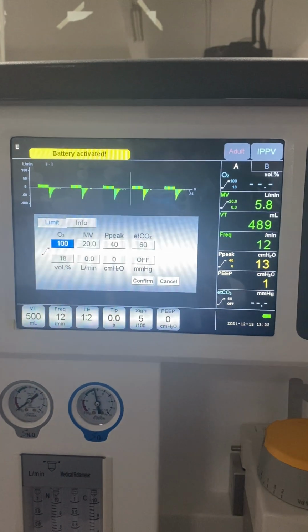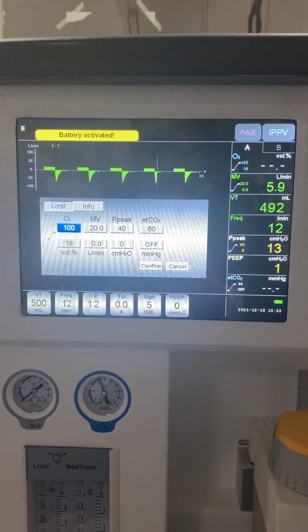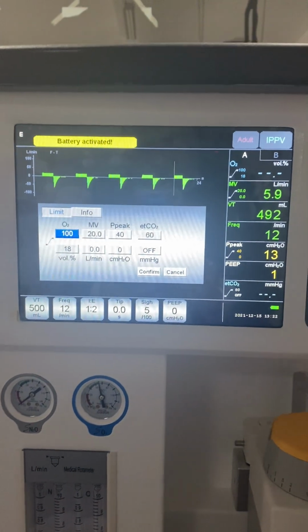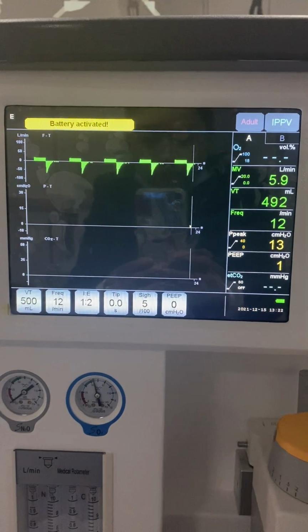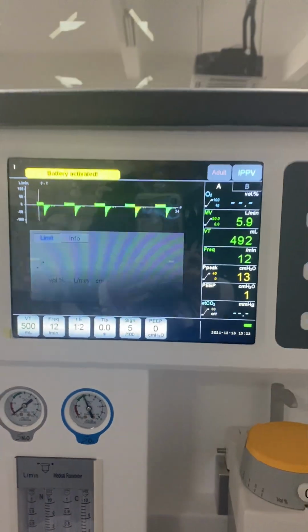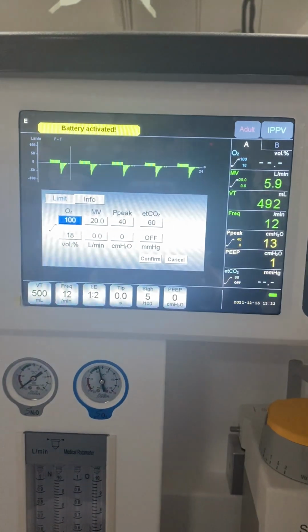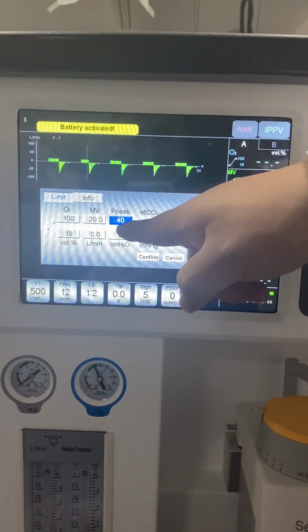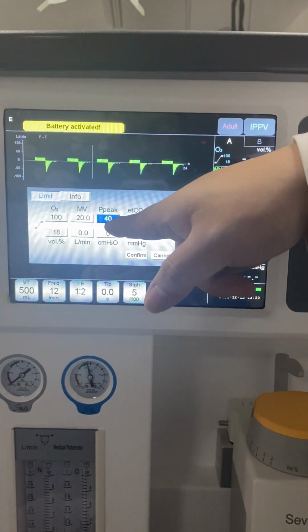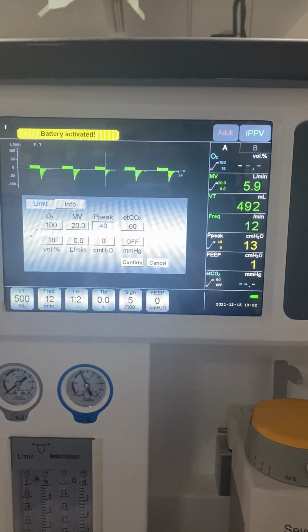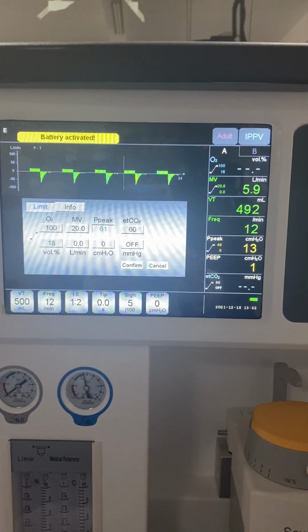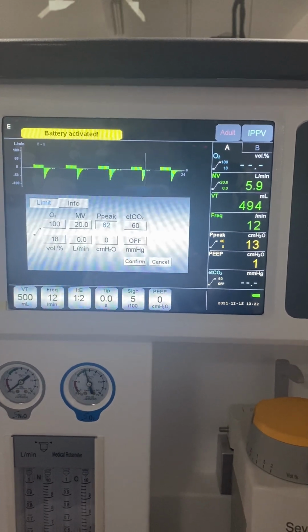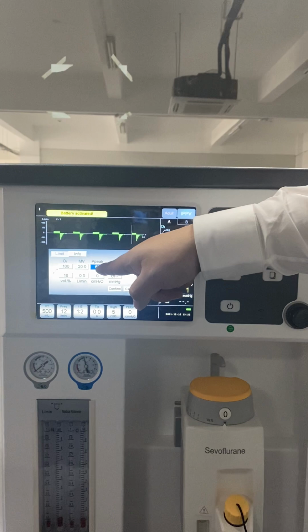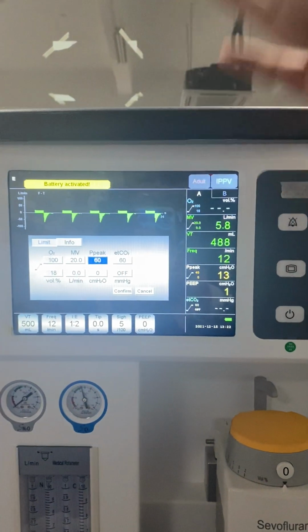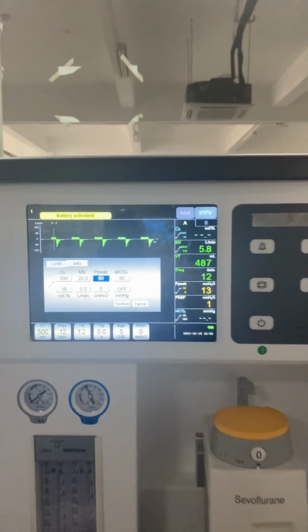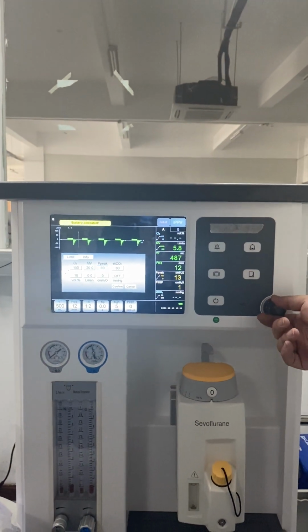Why do we need to set this? Usually, when you get the machine, you don't need to care about these settings. But for example, if sometimes we get a patient who is very fat and we need very big parameters, then we need to set the pressure here. For example, if I set it to 40, it means if the pressure is more than 40, the machine will give alarms. But if some patient needs more pressure, we can just press this. For example, now I set the upper limit to 60. Then it means only if the pressure is more than 60 will it give an alarm. So you can set it for different kinds of patients.